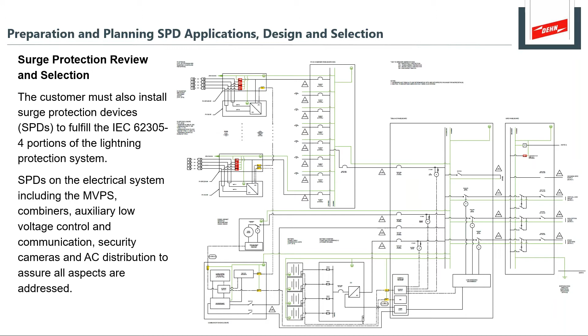Okay, so in preparation, you're planning, looking over your electrical diagrams, looking for where you want to find SPDs. The placement of surge protection devices matters, and there are many guidelines for this - it's easy to go to the IEC standards, NFPA, and UL standards to get guidance on where to look for surge protection, lightning protection, earthing, and bonding. You're looking at the electrical diagrams for the plant in advance, planning where you should see SPD devices. It'll show on the schematics, though if they're out of date it may not show your surge protection devices - but these are the targets you'll be looking for in your planning. It's good to understand the overview of the site. It's not always possible, but this is part of your planning.